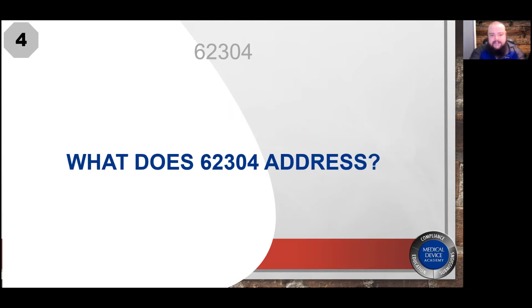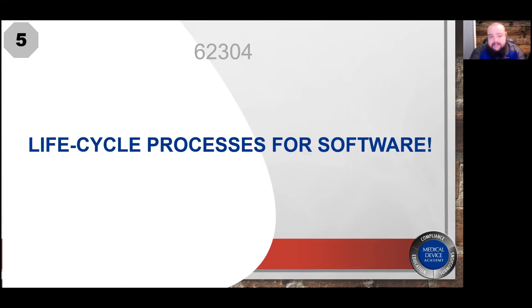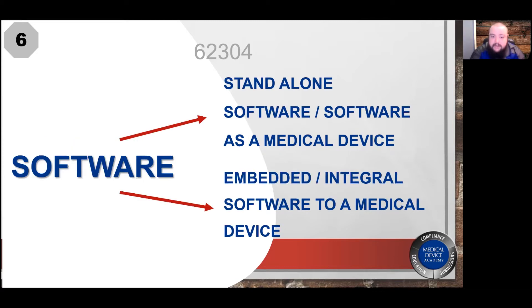So what exactly does 62304 address? It may sound self-explanatory, but it covers lifecycle processes for software — and when discussing software, that includes both standalone software or software as a medical device, as well as embedded software or software that is integral to the function of a medical device.